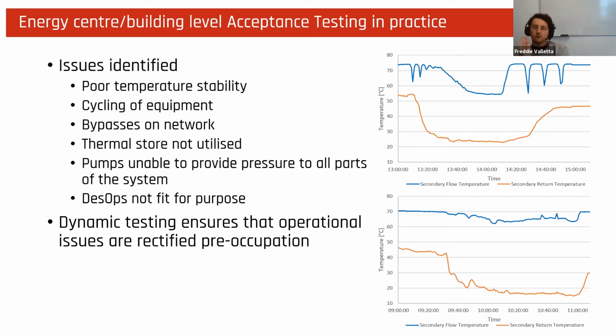Once these issues were investigated and the changes were made, the fluctuation was completely eradicated on a reiteration of the load test, and the secondary flow temperature didn't drop nearly as much as the first time. This was then rectified further on the day to ensure that this secondary flow temperature remained stable and the risk of heat delivery at elevated demand was drastically reduced. This dynamic and iterative testing ensured that these operational issues were again rectified pre-occupation.